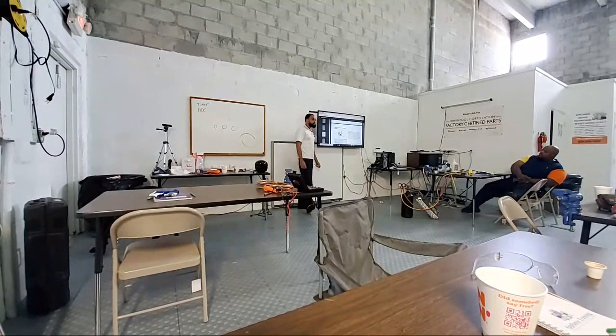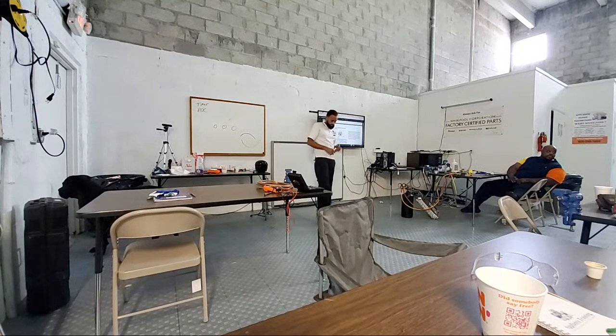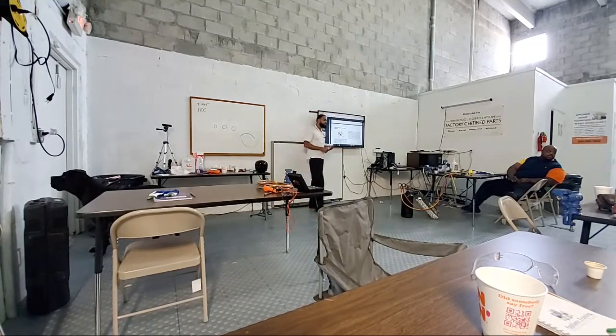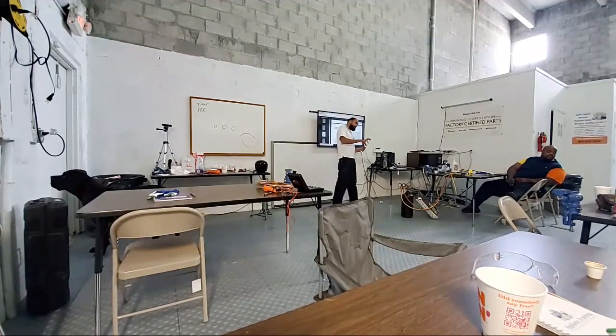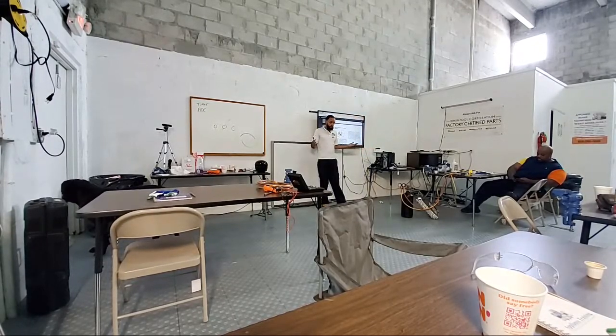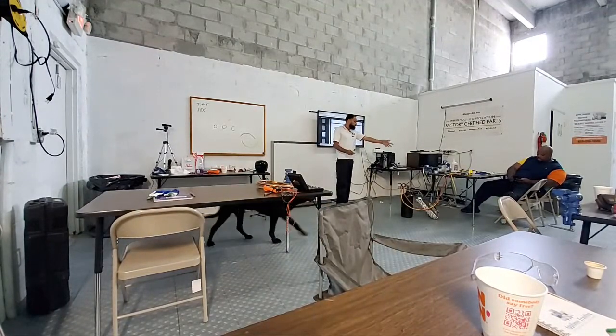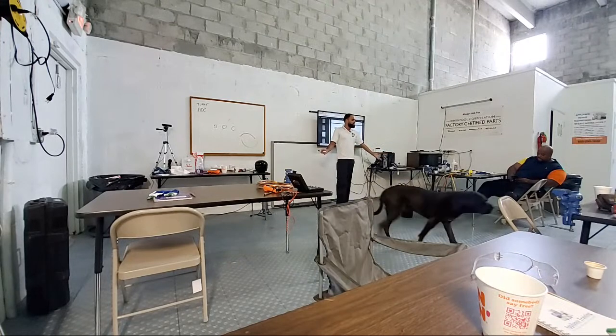So, Mr. Frank, I just want to make sure I'm clear that the bimetal is standing up and sitting on top of the evaporator, and you have it upside down when you spray it. No, you turn the can upside down and you spray it. The bimetal, you leave it how it is. Spray that, and what you're looking for is for it to close. Not activate, close. Open or close, that's the only word. Okay, so when it closes, that means the defrost is going to kick on. Now, if you spray it, it will kick on. Well, no, not that it will kick on. Your voltmeter is going to give you continuity.